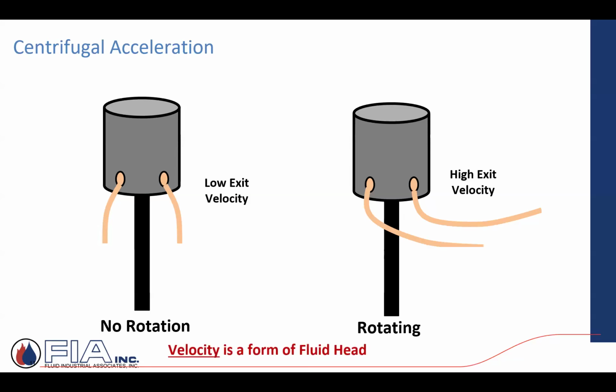So it's kind of a simple, silly little drawing, but it's saying here, if I had this can filled with water, and I had these holes at the very bottom, and I had no rotation as in that picture on the left, the water would drain out of it at a certain velocity. Just the weight of the water is the motive force. If I add rotation and start spinning it fairly rapidly, and I'm adding velocity, it's centrifugal. I have rotation around a rotor, and I'm adding this energy. That water is going to exit those holes at a much higher velocity. It's a very simple drawing, but at the end of the day, that's the operation of an impeller inside the volute of a centrifugal pump.